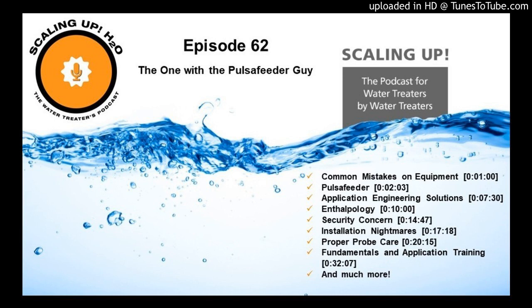The city of New York has additional requirements that make being a water treater without online controllers very difficult. You'd have to be at that account the exact second you got a test result showing positive to make that change. So the only way those guys can go home is to have their controllers online. If they don't, the testing interval goes up dramatically to an almost unsustainable level.